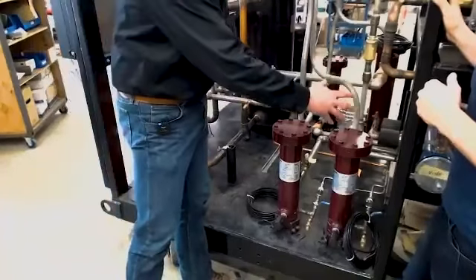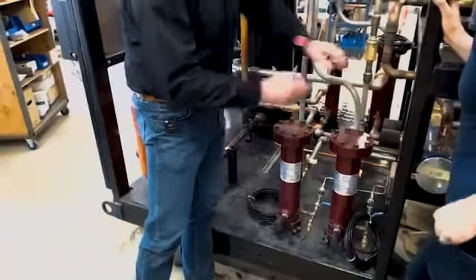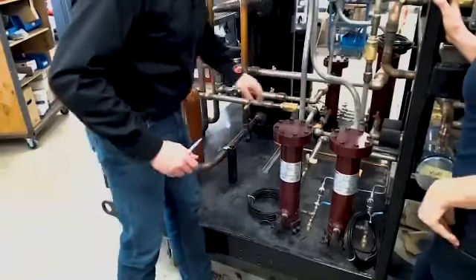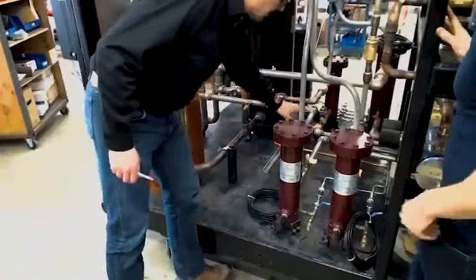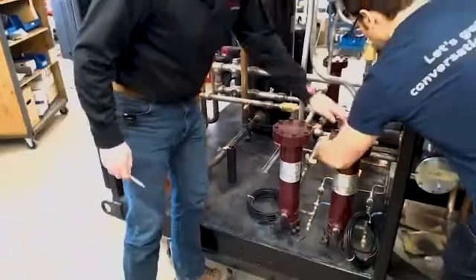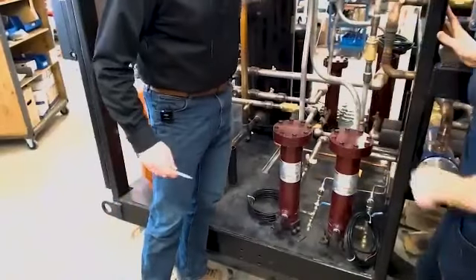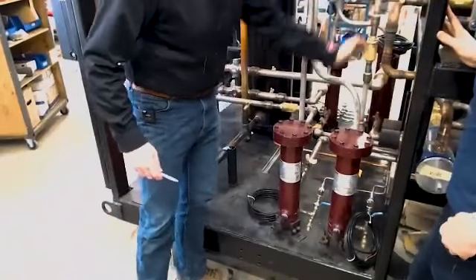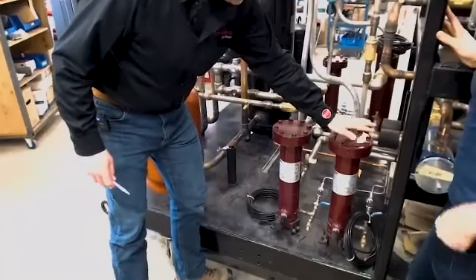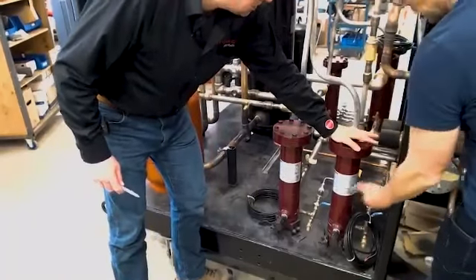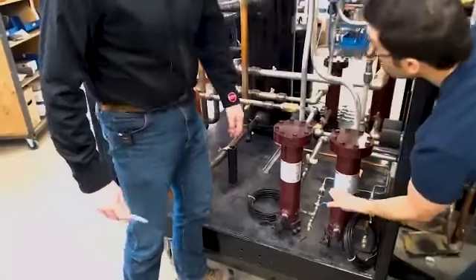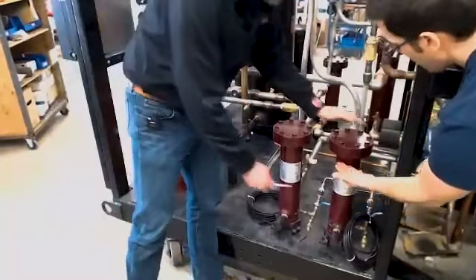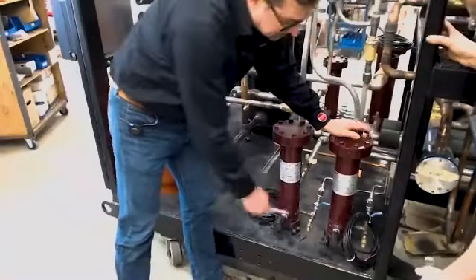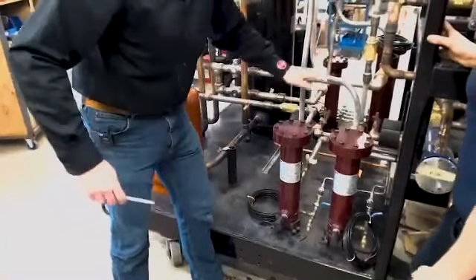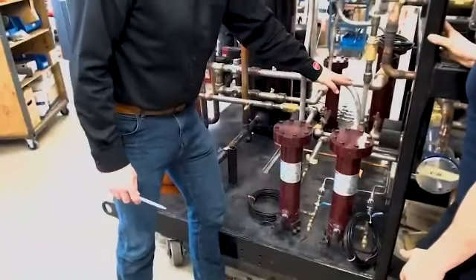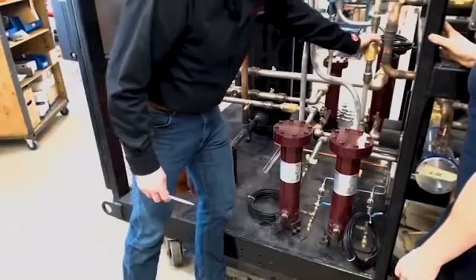So if I'm going to pump out suction groups, I got to put a check valve here. You'll notice all Arneg machines are going to have a check valve on the outlet of the oil separator. Yeah. So this is for the reason, if this machine goes off and sits idle, gas can migrate back and condense while the machine is off, or while the suction group is off, inside the temporary oil separator. So that would actually fill up? That's right. Wow. And then when we start the machine up, we're going to create thermal shock inside the oil separator, which could cause significant problems to the machine. Yeah. So cold startups are never favorable. So we put the check valve here.